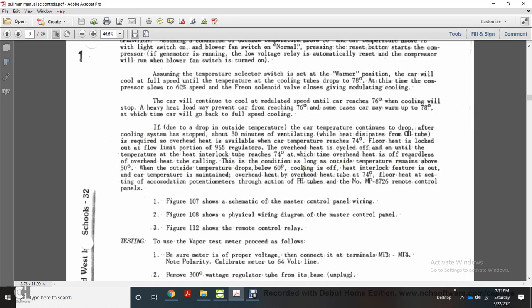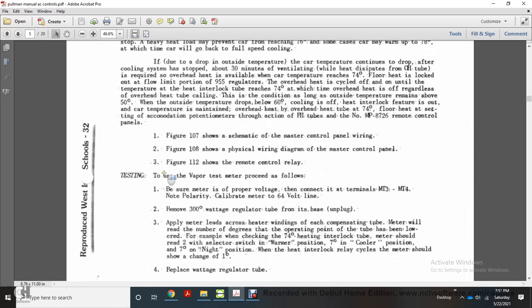If due to dropping outside temperature the car temperature continues to drop after the cooling system stops, approximately 30 minutes of ventilation allows heat to dissipate. The overhead heat tube requires that overhead heat be available when car temperature drops to 74 degrees; floor heat is locked out by the flow limitation portion of the 955 regulator. Overhead heat cycles off until the heat interlock tube reaches 74 degrees, at which time overhead heat is off regardless of the overhead heat tube condition, as long as outside temperature remains above 50 degrees. When outside temperature drops below 50 degrees, cooling is off, the heat interlocking feature is out, and car temperature is maintained by overhead heat tube at 74 degrees, with floor heat governed by accommodation potentiometers through the FH tubes and MP8726 remote control panels.